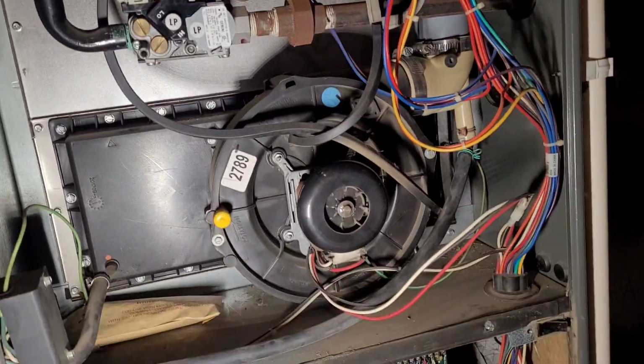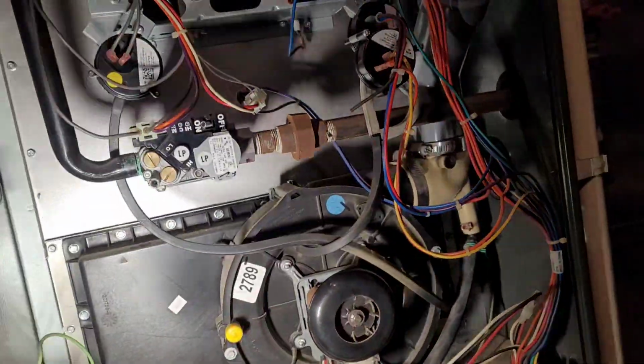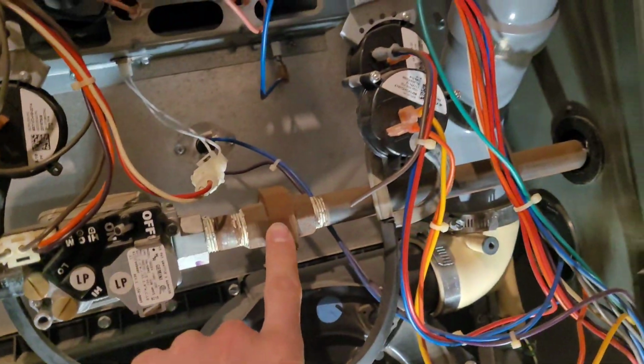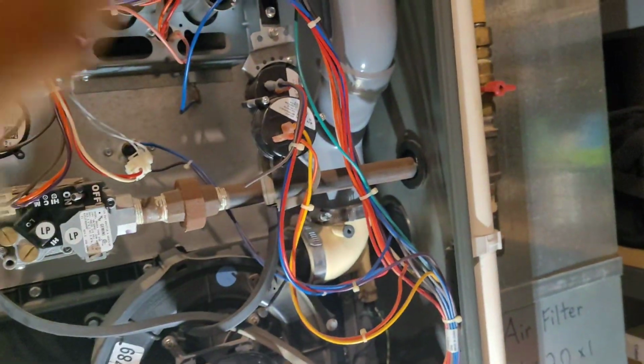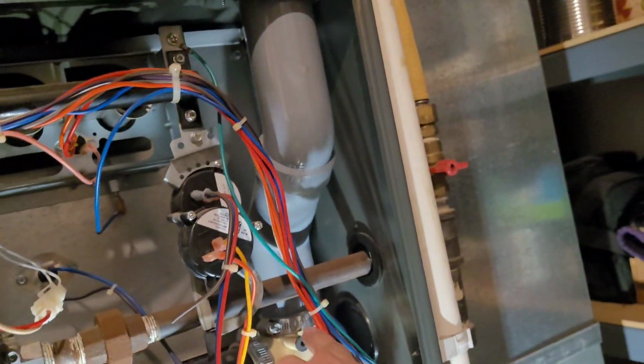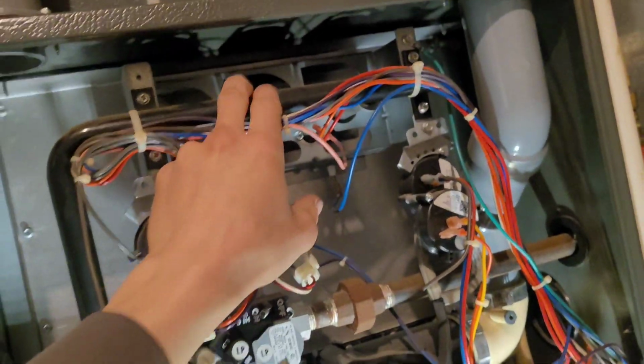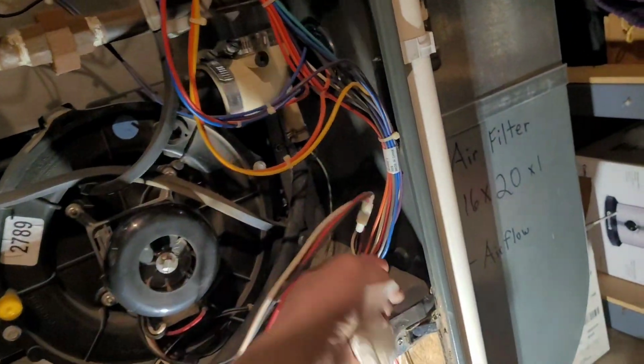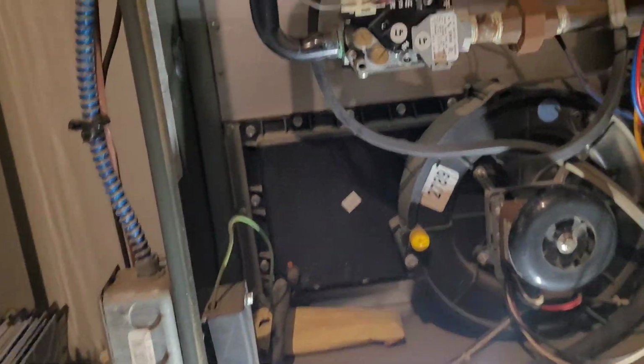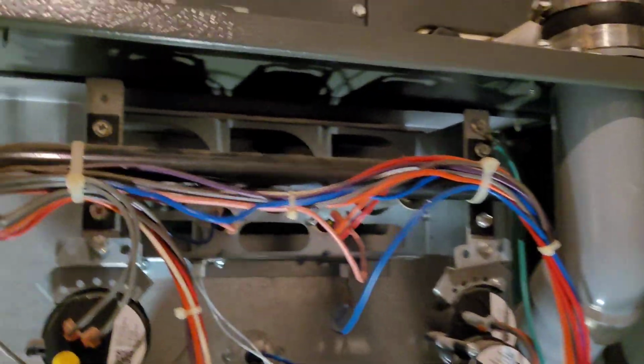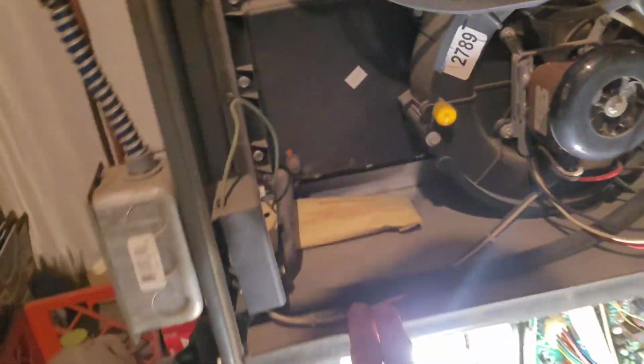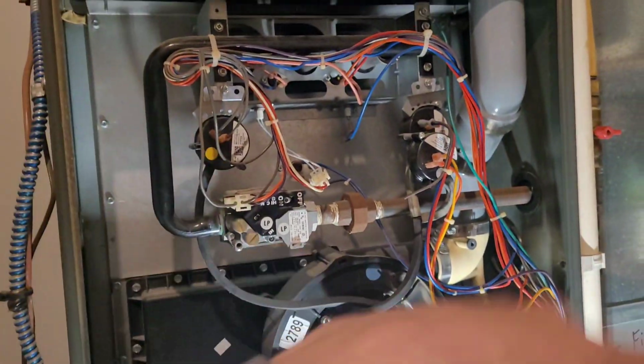So in order to remove the heat exchanger on this, we pretty much have to take everything out of here. So we're going to disconnect this union, thread this nipple out of the gas line. We're going to pull this vent off and remove this entire fitting out the top. Pull the combustion blower, pull the burners, pull the manifold, get all that stuff pulled. And of course disconnect this tubing and take out all the screws that go around the perimeter of the heat exchanger, and then there's 3 from the top, and I believe there's 3 from the bottom. Actually no, we don't have to remove any from the bottom. So, fairly straightforward. I'm just gonna time-lapse pulling this all out of here.